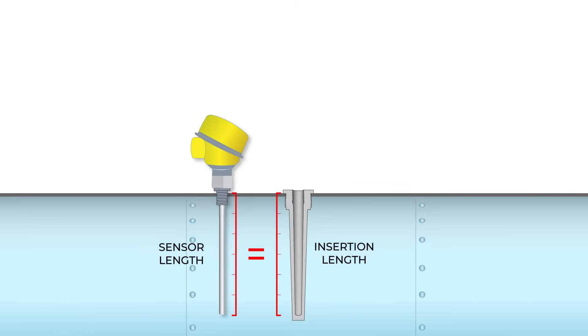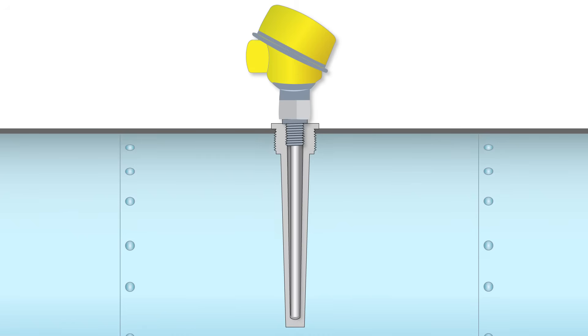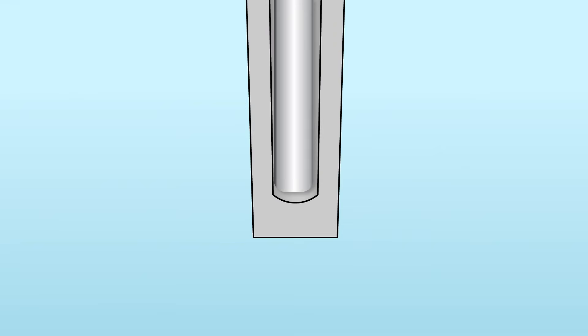A temperature sensor equal in length to the thermal well's insertion length is inserted into the thermal well opening on the outside of the pipe or tank using the entire insertion length of the thermal well. The tip of the temperature sensor must be within close proximity to the bottom end of the thermal well for best results.